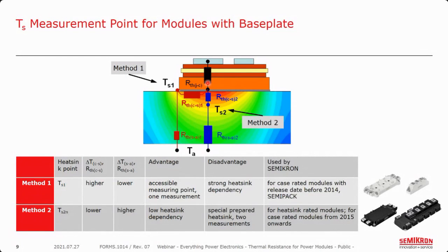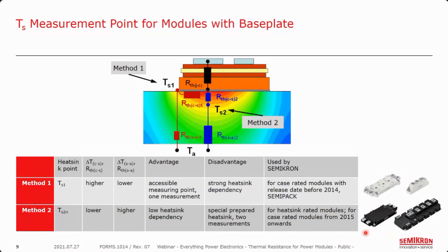Semikron has used both methods. In the past, for our base plate modules such as SEMiX with spring pins, we used method one. This method is still used for our thyristor and diode modules such as the SEMIPACK family. Since roughly 2015, all new IGBT modules use this reference point below the module. And to reiterate, all base plate-less modules — such as the MiniSKiiP — have always used the heat sink temperature beneath the module, method two. If you have any doubt about where the measurement point is for a particular module, please consult the technical explanations document for that particular product line.